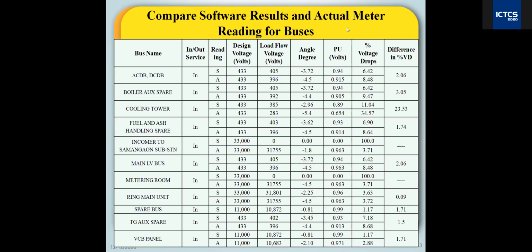Likewise, at the cooling tower, you can observe that there is actually a 34.57% voltage drop expressed, and the software detected 11.04%. So there is a 23.53% voltage drop improvement possible, so we can save energy here, since otherwise it would go into loss.